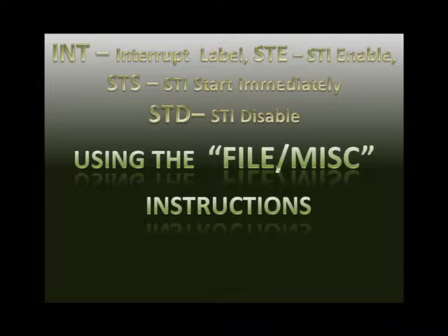Now, for the MicroLogix, especially the 10-point MicroLogix 1000 that you're probably using with this lab book, not only are the data files pre-declared, they're also pre-expanded to their maximum size. Also, ladder 5 is labeled STI_INT, selectable time interrupt, interrupt routine. This is the only location that you can place logic that you would like to execute on a periodic basis, determined by the value that you put into the register S2:30, which is the set point or the preset value for that timer.